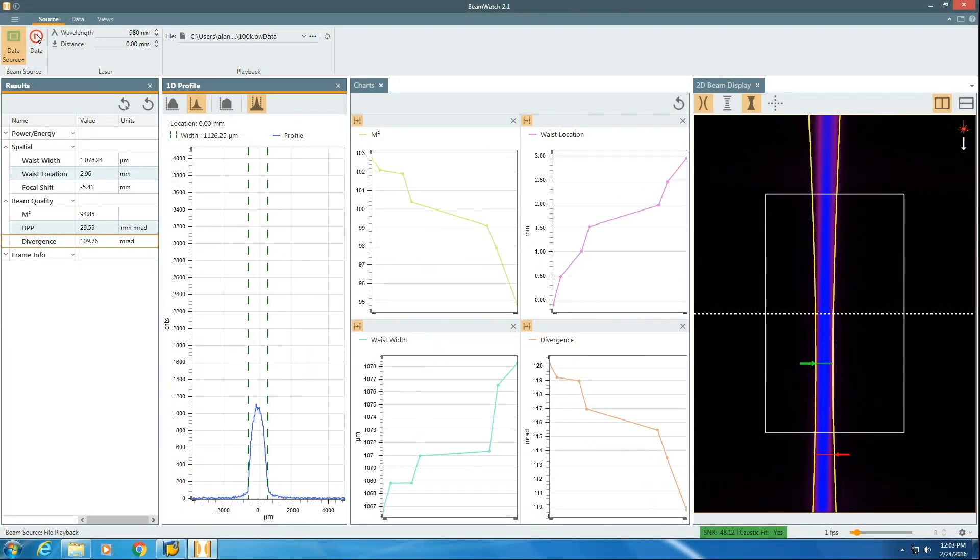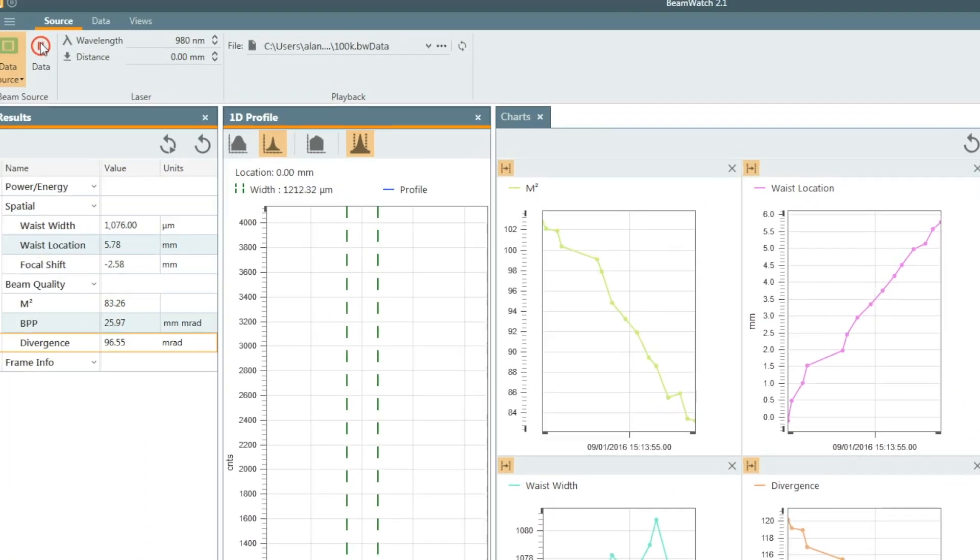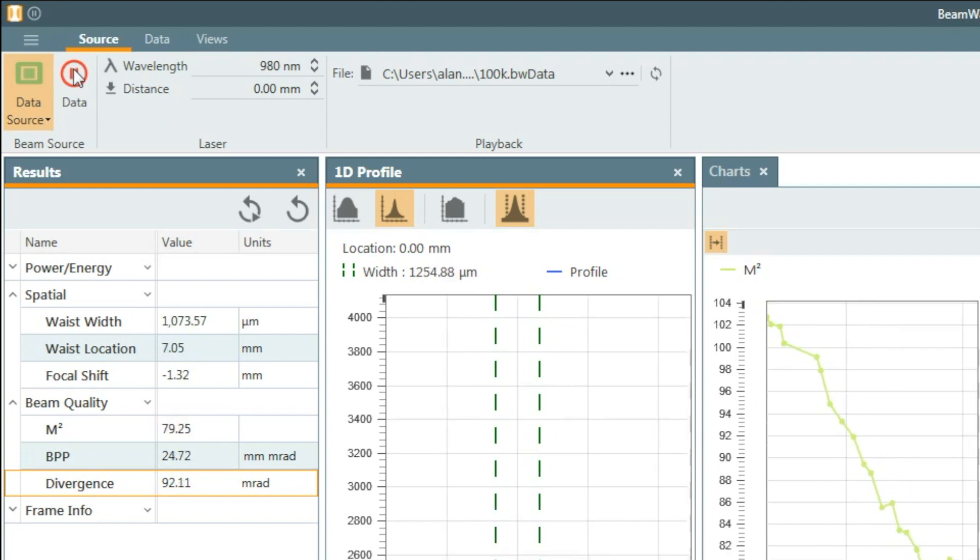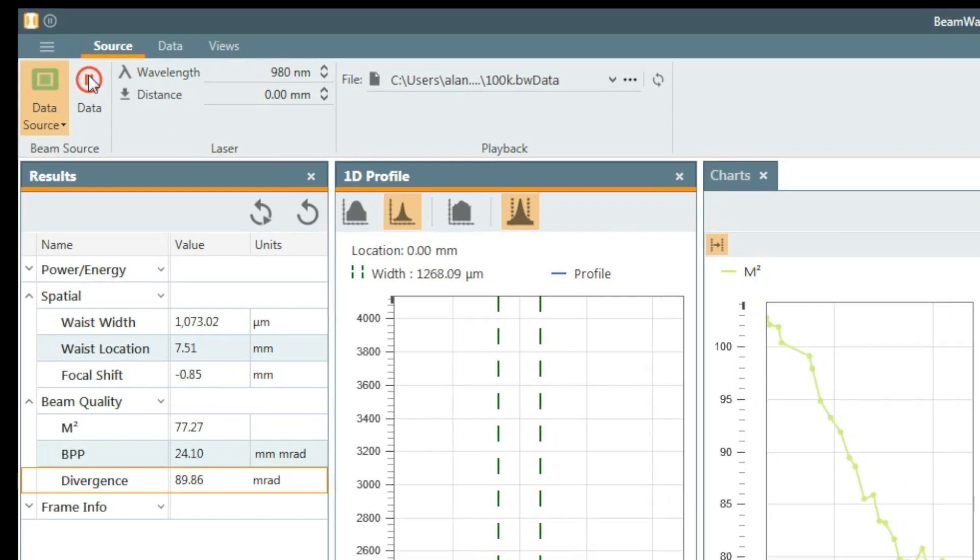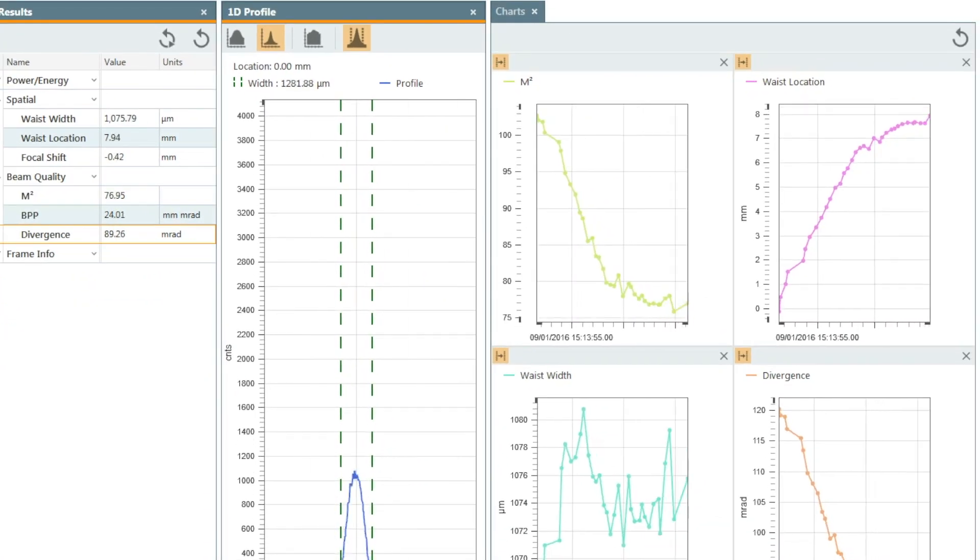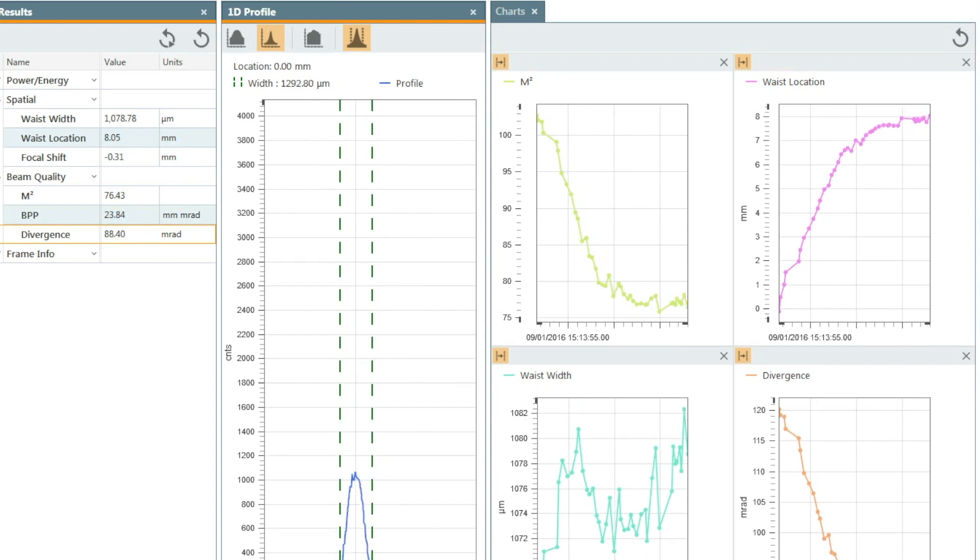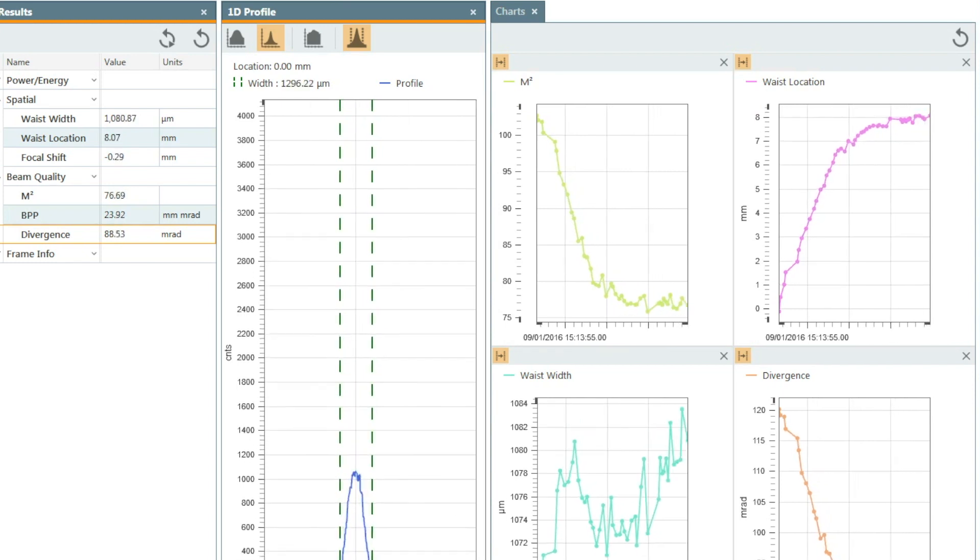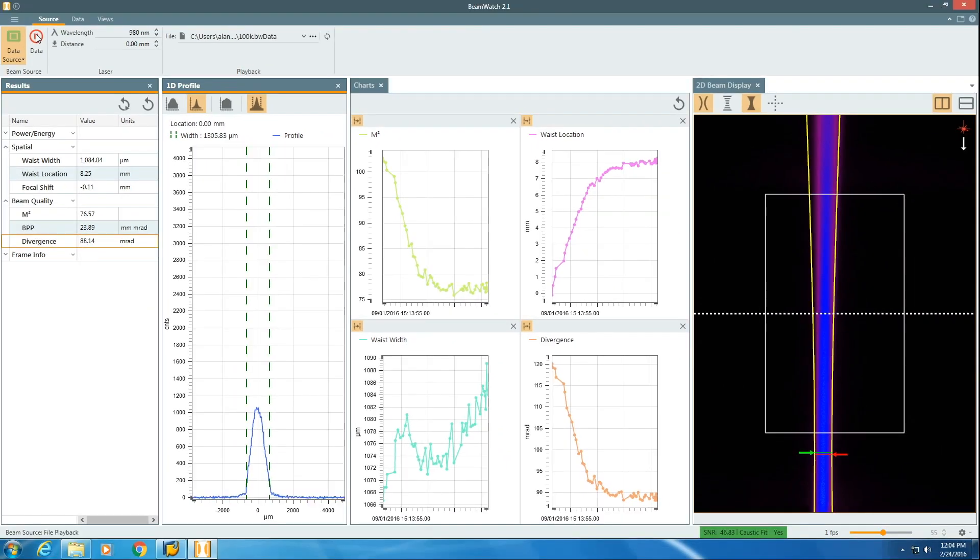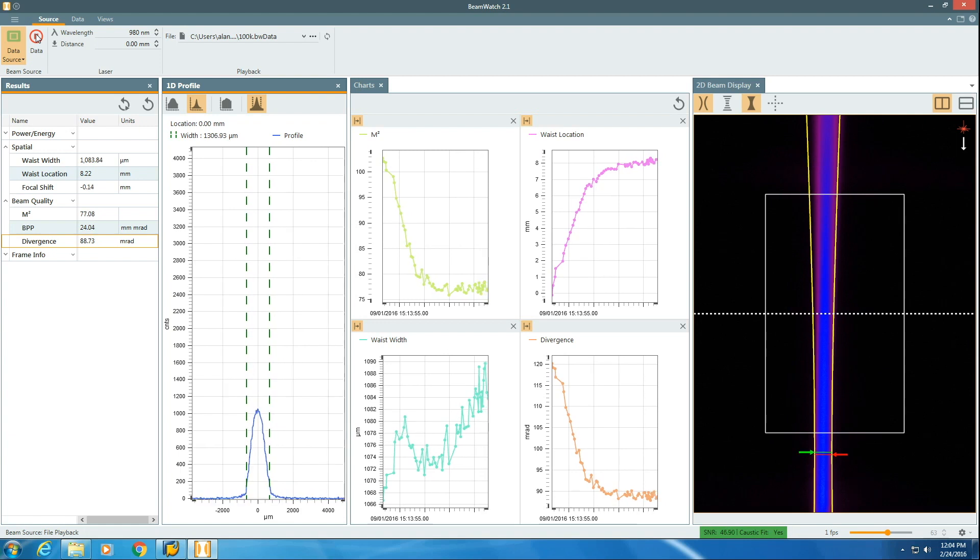Because beam watch is measuring many images per second, all measurements are dynamic. These measurements include beam waist size, beam waist location, and beam propagation measurements such as divergence, M squared, and beam parameter product.